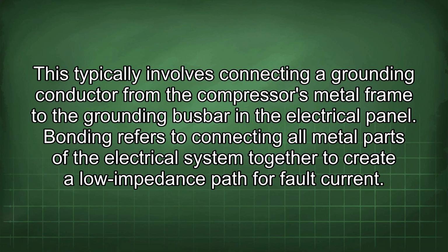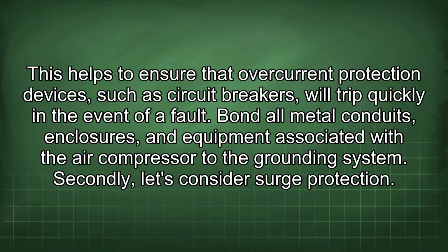Bonding refers to connecting all metal parts of the electrical system together to create a low impedance path for fault current. This helps to ensure that overcurrent protection devices, such as circuit breakers, will trip quickly in the event of a fault. Bond all metal conduits, enclosures, and equipment associated with the air compressor to the grounding system.